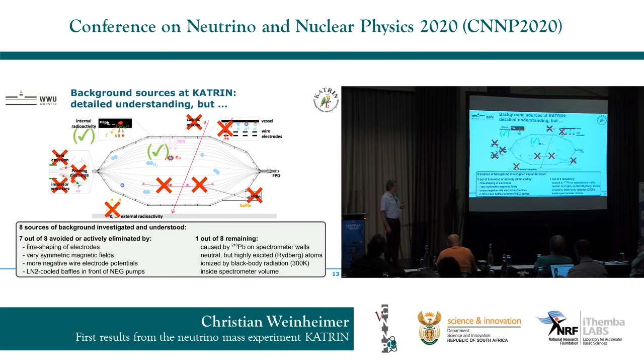That source are lead-210 daughter ions implanted by radon-222 decays in the air during commissioning. That is everywhere there. And this radon, this lead-210, when it decays, it has a chance to eject highly excited neutral atoms, so-called Rydberg atoms, which can overcome our barriers of electric and magnetic fields. And they can be going through the spectrometer and on their way be ionized by the black body radiation of the spectrometer at 20 degrees Celsius. And then it frees electrons. It takes little energy. The infrared radiation of all these walls here would be enough to ionize, and then it frees electrons which run down the electric retarding potential, and it's been detected here.